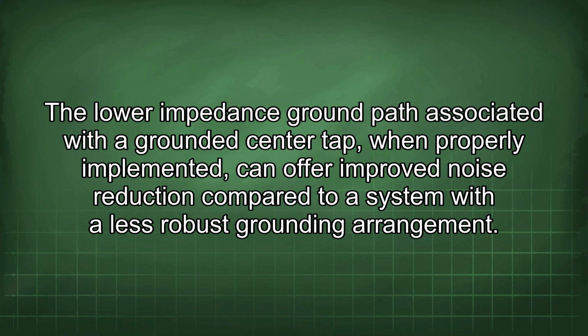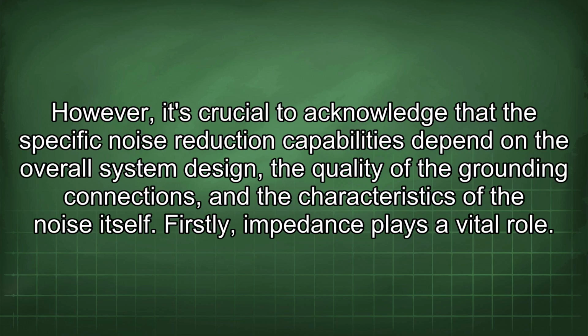The lower impedance ground path associated with the grounded center tap, when properly implemented, can offer improved noise reduction compared to a system with a less robust grounding arrangement. However, it's crucial to acknowledge that the specific noise reduction capabilities depend on the overall system design, the quality of the grounding connections, and the characteristics of the noise itself.